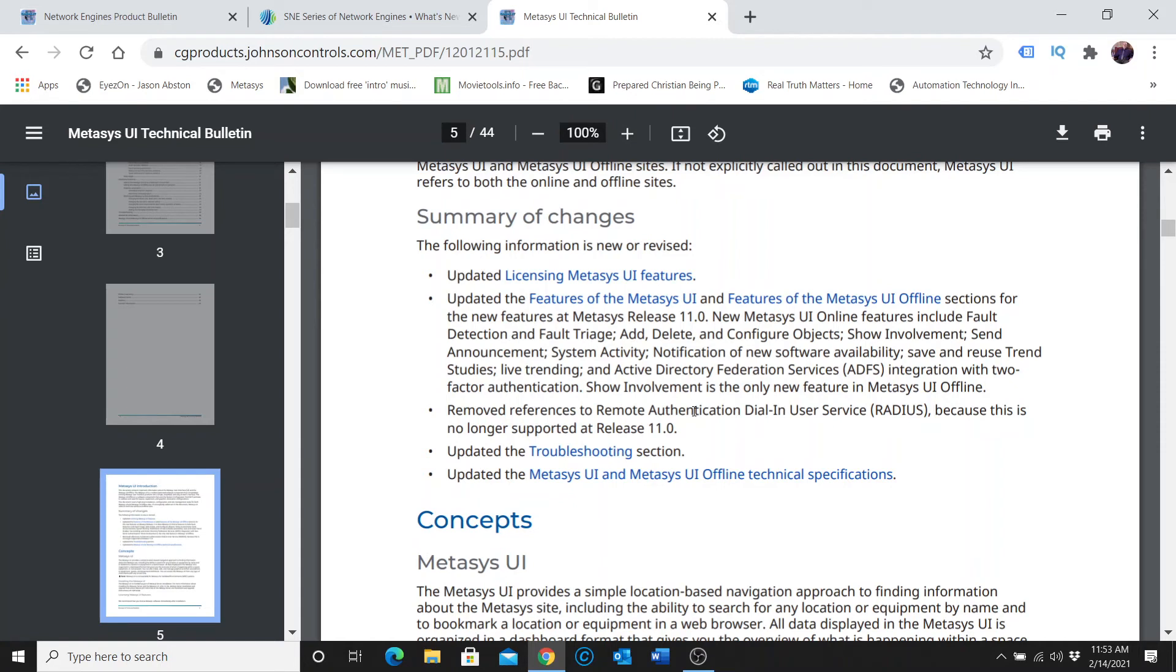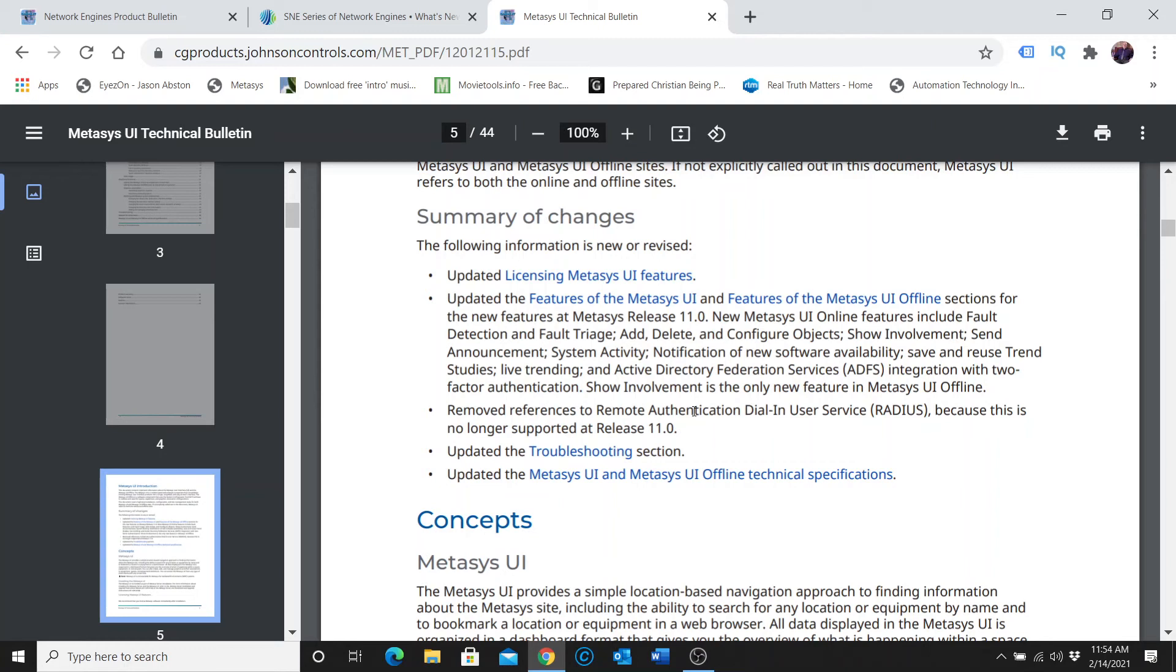Also, if you are interested in upgrading your system or changing your system, now is a good time to start making plans for the future. We all know that N2 is going away. A lot of the older legacy devices are no longer supported, and they haven't been for quite some time. The newer devices will talk on an N2 trunk or an N2 network. Now, it's been our experience that they typically will start slowing down the N2 network. And, you know, I can't say that for everyone, but that just seems to be our experience with them. So, that's something else that you may want to consider as well.